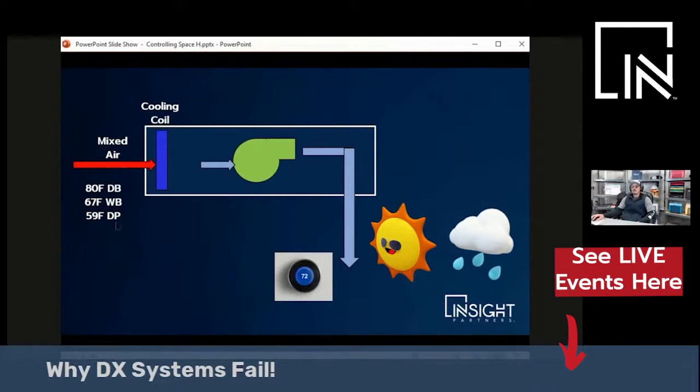So the dew point of this air is 59 degrees. Here's what's important. To dehumidify this air, the cooling coil needs to be at a lower dew point than the dew point of the air. So if this cooling coil is, let's say, 45 degrees, you'd probably get about 52-degree dry bulb off the coil. So the temperature of this coil is colder than the dew point of the incoming air.